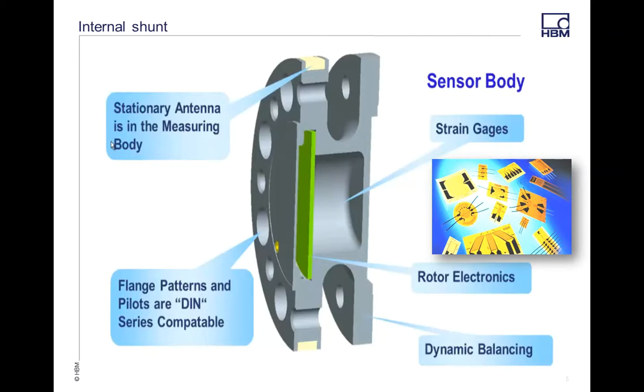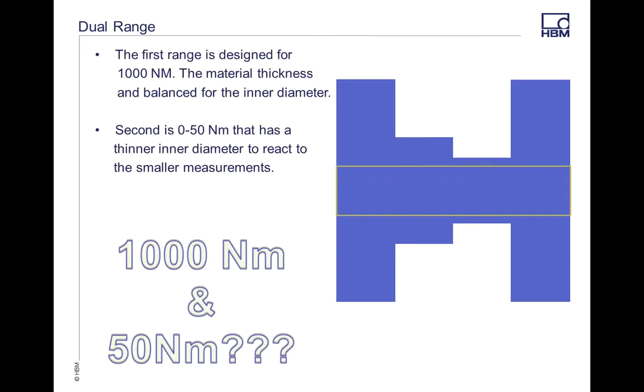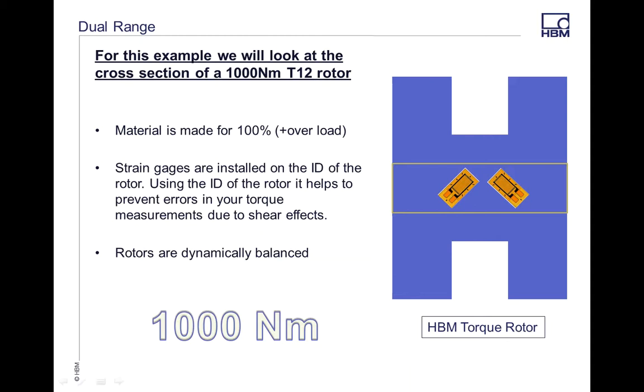Let's dive into this rotor a little bit and figure out if there's an actual dual range. On our rotors themselves, they're all machined and balanced for a specific range. In this example, I have a 1,000 newton meter transducer. The metal that's on the actual transducer is set up for the 1,000 newton meters. That's the normal range.